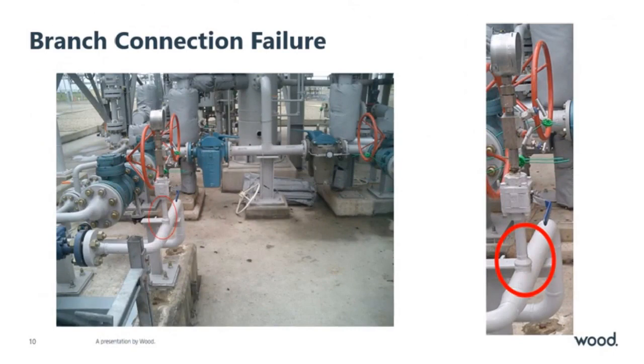So one of the problems early on was a failure of a weld, and that's quite serious. So we've got an integrity concern. You can see a tall vent pipe with a heavy instrument block bleed. So if I just highlight that, there's your instrument. Well, there's your valve, then your instrument block bleed there. On the right-hand side, you see a zoomed-in photo. So it's a perfect recipe for some reactive motion from a resonating vibration. So what was causing it?